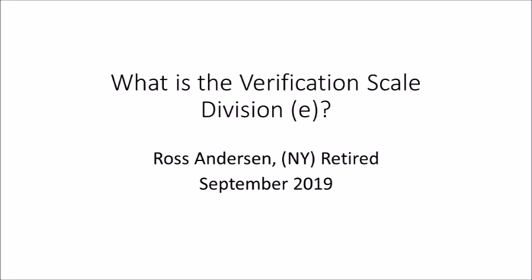Verification is applicable to any instrument. And so what I propose to do is look at verification, the verification scale and the verification scale division in terms of another type of instrument, and the instrument I chose is the motor fuel device.